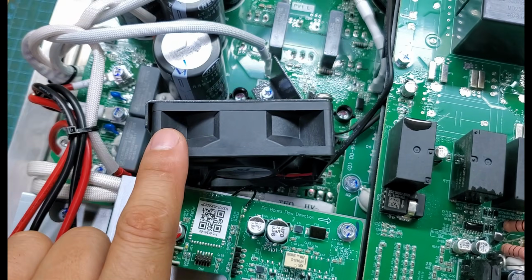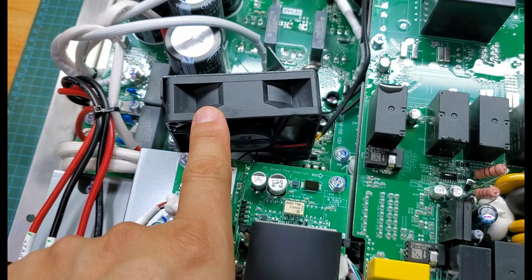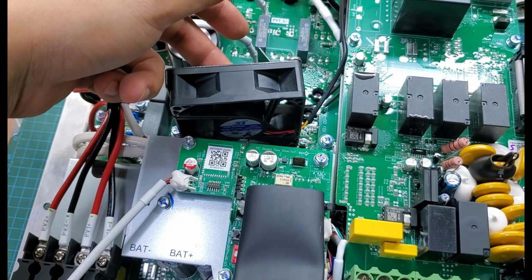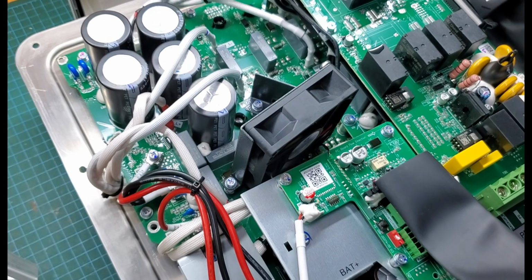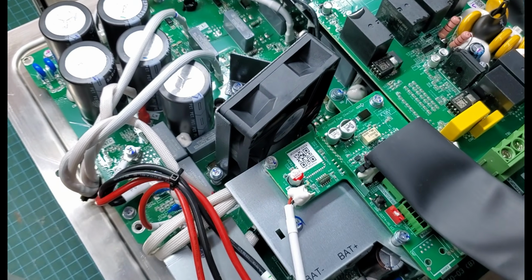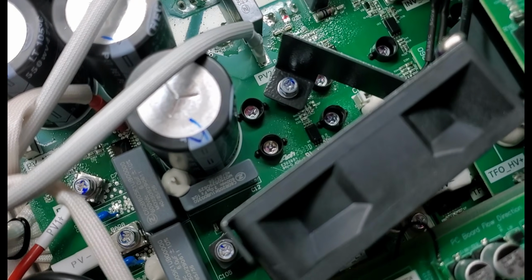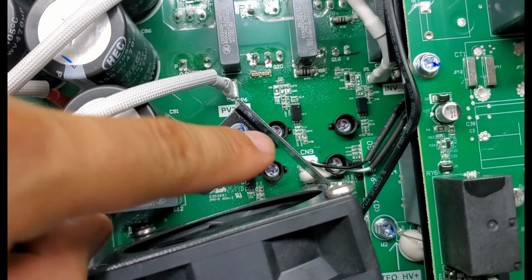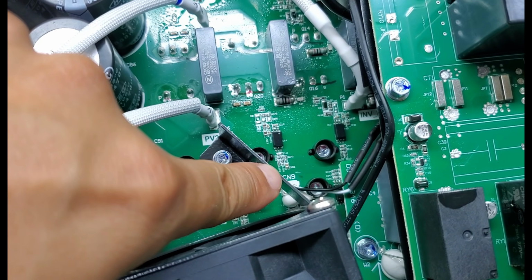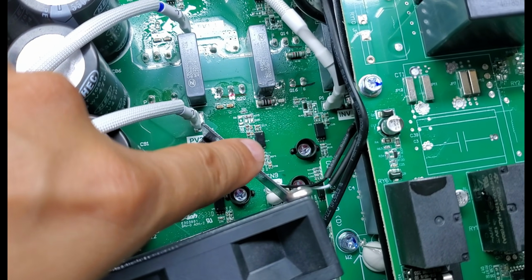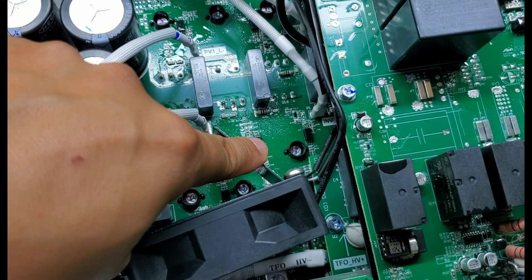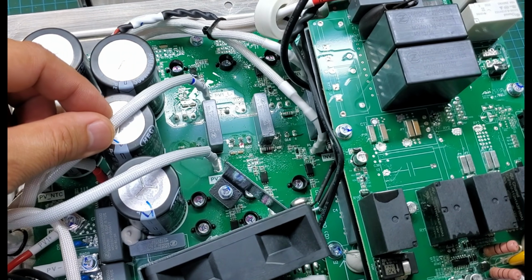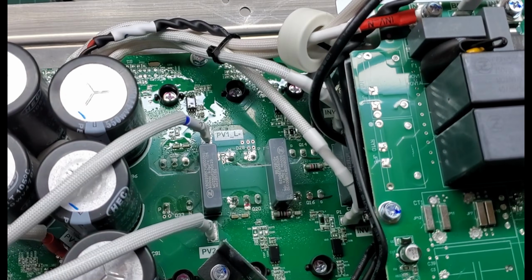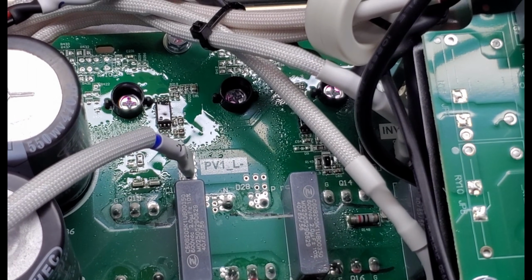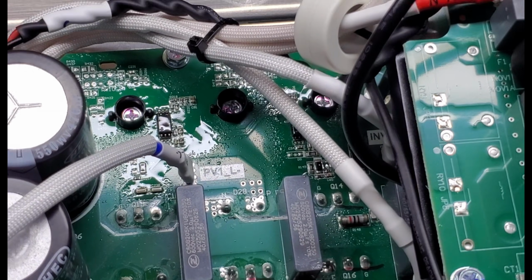A cooling fan is used to circulate air inside the inverter, creating airflow to carry heat away from components like the capacitors and other internal parts. This warm air transfers heat to the inverter's enclosure, which then gradually dissipates it into the surrounding environment. Right here under my hand are the IGBTs and diodes for the two MPPT modules. With just two IGBTs and two diodes, this inverter is capable of handling up to 9 kilowatts of PV input power. Pretty impressive.